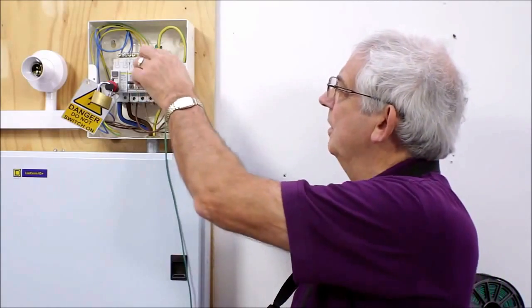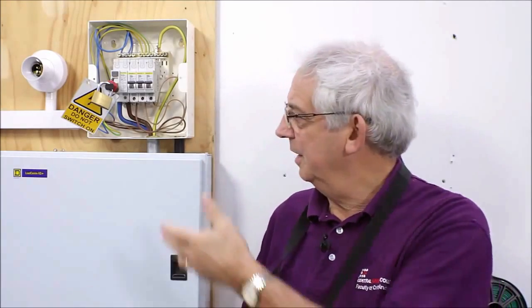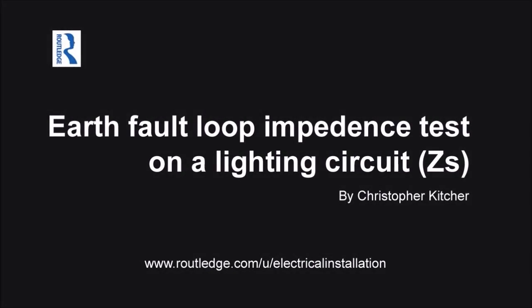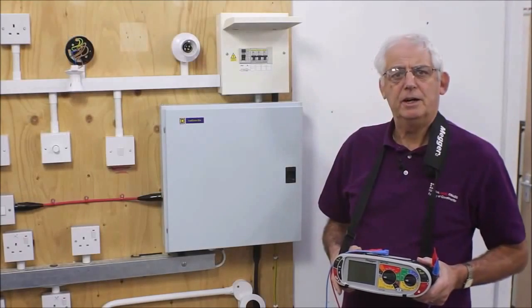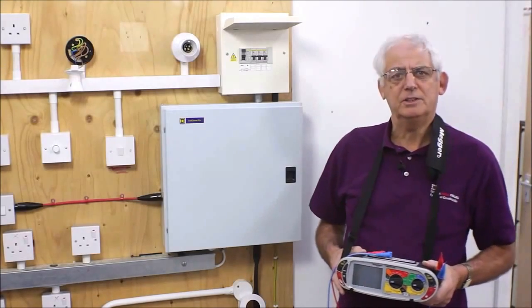Once I've completed the test, obviously I'll remove the leads, make absolutely certain that I reconnect the earthing conductor, and then at that point I can take off the padlock and reinstate. What we're going to do is carry out a ZS test on a lighting circuit.